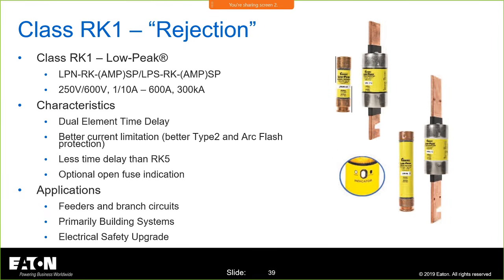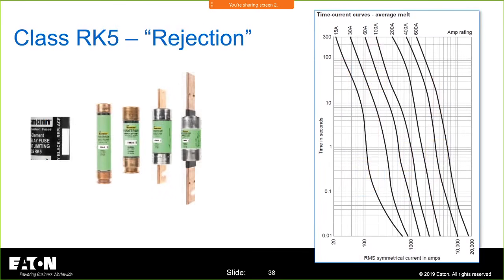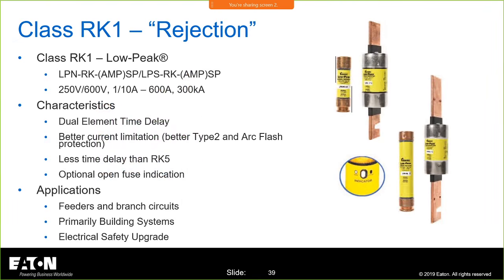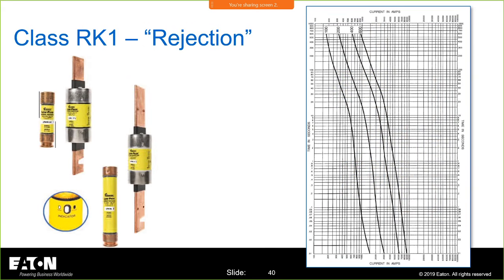All right. So this is your RK1. Again, rejection, but you have the ones and the fives, and you're talking about a difference in trip curve. So remember the RK5. Remember in your mind the slope of that curve. And when you talk about an RK1, which has a lot of the same stuff, goes up to 300,000 amp interrupting, all the same type of things, but look at what that curve looks like. It's a lot different. It's not as sloped. It's a little bit more vertical, right?